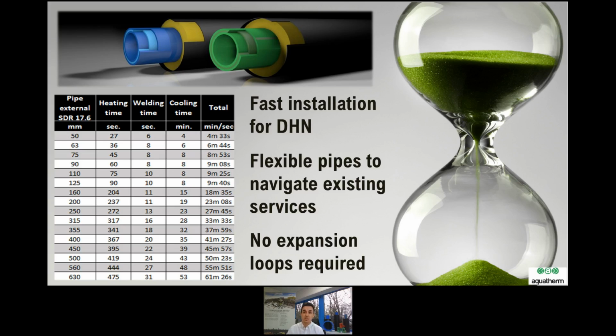Only fibre composite pipes are used as the medium pipe, which, due to their low linear expansion, are ideal for laying underground. All Aquatherm pipes are made of the corrosion-resistant material Fusiolen PP-R, which is characterised, amongst other things, by very good weldability and a high inherent insulation value, and the low weight makes it easy and safe to install on site. You'll see the impressive welding times within the table on the slide, which are significantly lower compared to the welding times of equivalent materials. The innovative nature of the fusilin within Aquatherm pipes ensures flexibility to navigate around existing services, which can lead to additional time savings during the installation process.